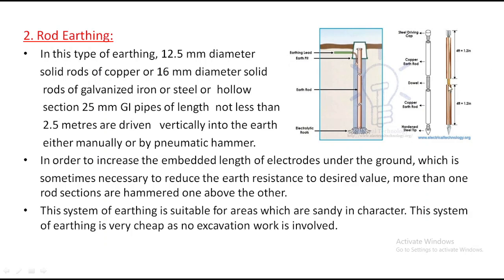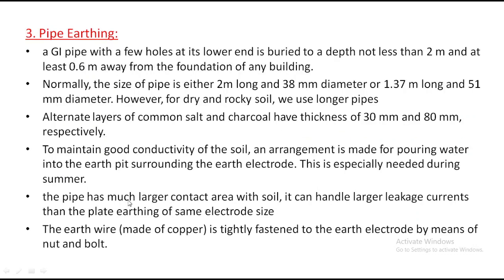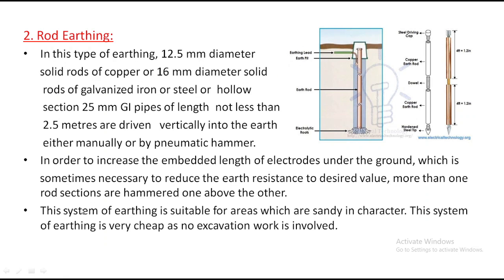Whenever we increase the rod sections, the impedance and resistance will automatically decrease, so the rating increases and more fault current will be grounded. Next, this system of earthing is suitable for areas which are sandy in character. Wherever there is sand, it is useful. The system is also very cheap, as no excavation work is involved. We use the rod directly, that's why there is no excavation work and why it is very cheap. It is useful in sand areas and it is very cheap.